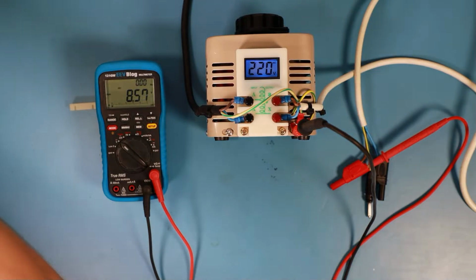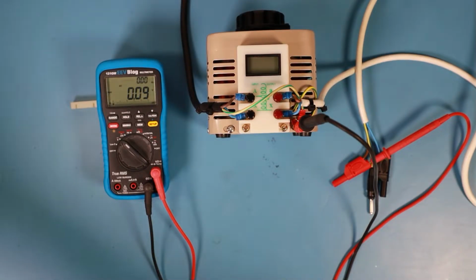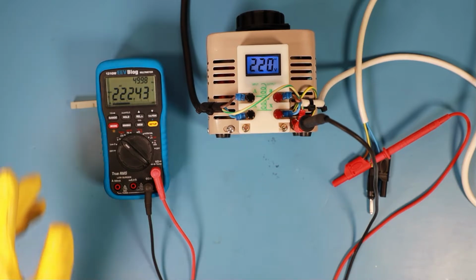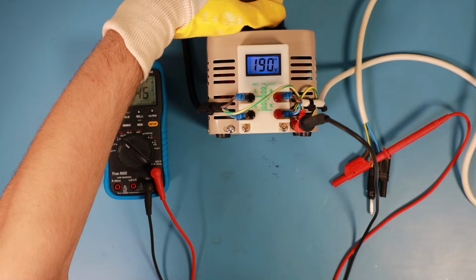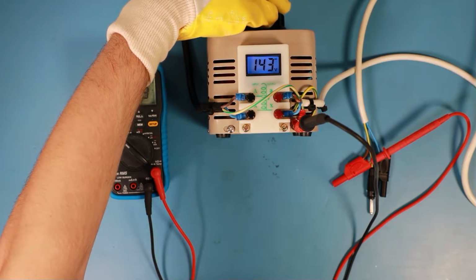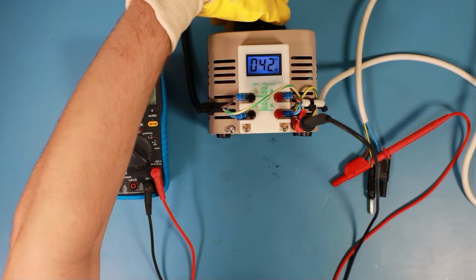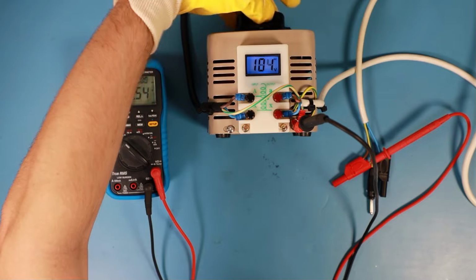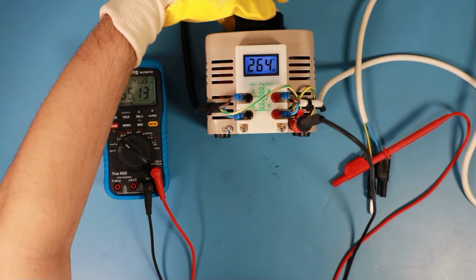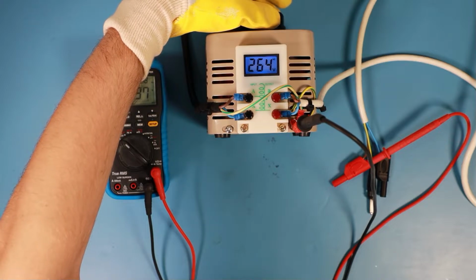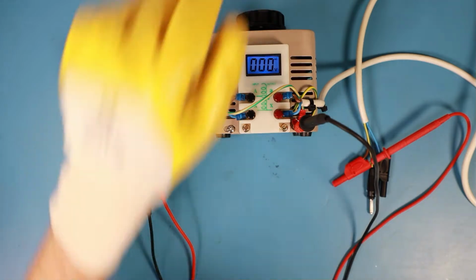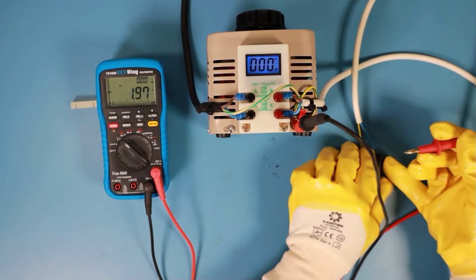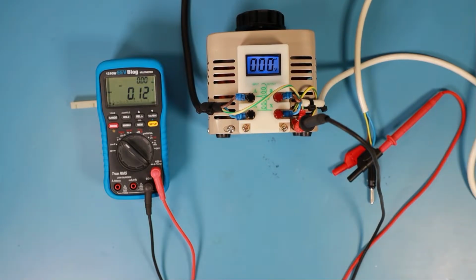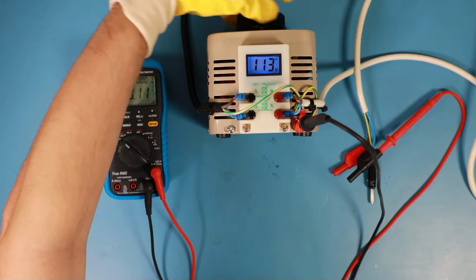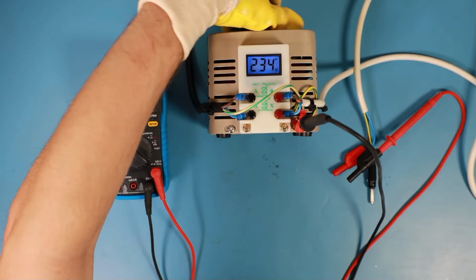Let me just do that. So now I have turned the plug around. So neutral and live are connected as they should. And you see on the phase, I have the same voltage as the voltmeter that's integrated into the transformer shows me. So I can go from 0 to even 265 volts with respect to protective earth. And when I connect my multimeter probe to neutral, I also get 0 volts, despite what I am selecting on the transformer itself.